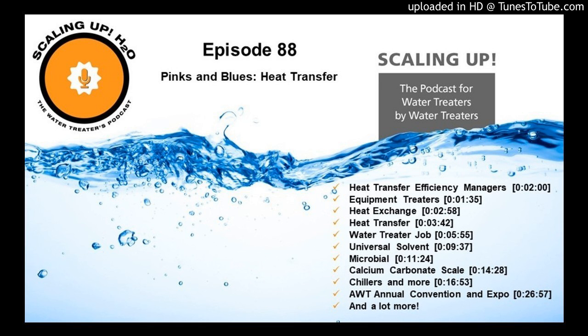Water is the universal solvent, so there's nothing we can do to stop water's potential to corrode, but we can slow that down, and that's what we do as water treaters. When it has all those dissolved gases in it, that enhances water's ability to corrode. So those are the 4 things that us water treatment folk have to deal with: corrosion, scaling, microbial fouling, and dirt and debris.